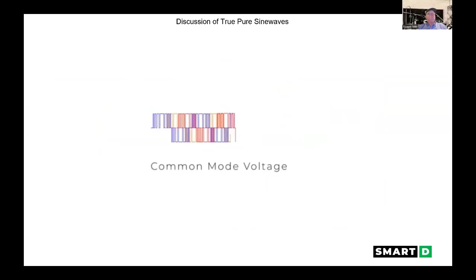Common mode voltage is created by VFDs switching IGBTs on and off continuously. This causes wear and tear on the motor bearings. The first sign of bearing damage is audible noise due to the bearing balls traveling over the pitted and frosted areas. How are these pitted and frosted areas created? Fast switching of the IGBT creates parasitic capacitances in the motor. Common mode voltage and capacitances are sources of a shaft voltage. Shaft voltage causes arcing through the bearing lubricant, which results in pitting on the bearings and fluting on the bearing races.